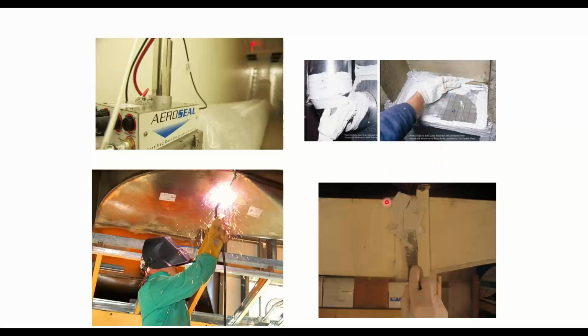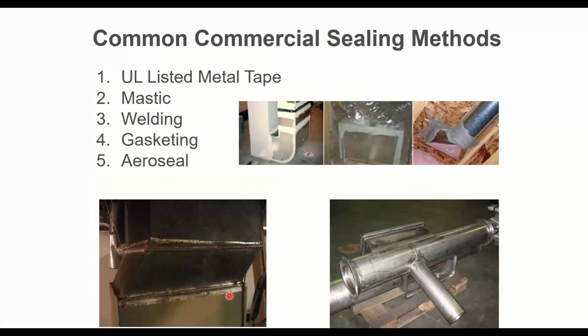But doing it with a glove is actually kind of the easiest way to do it, because when you're using the mastic, you don't just want to take it like we did in the bottom drawing here and just paint it straight down. All that does is put a layer of goop on each side of the duct. But I need the goop in the middle, in the cracks. So by using it with a glove, you can use your fingers to actually work the mastic into the cracks. That is the preferred way to do it, and that's going to give you the most likely chance of passing a duct leakage test.